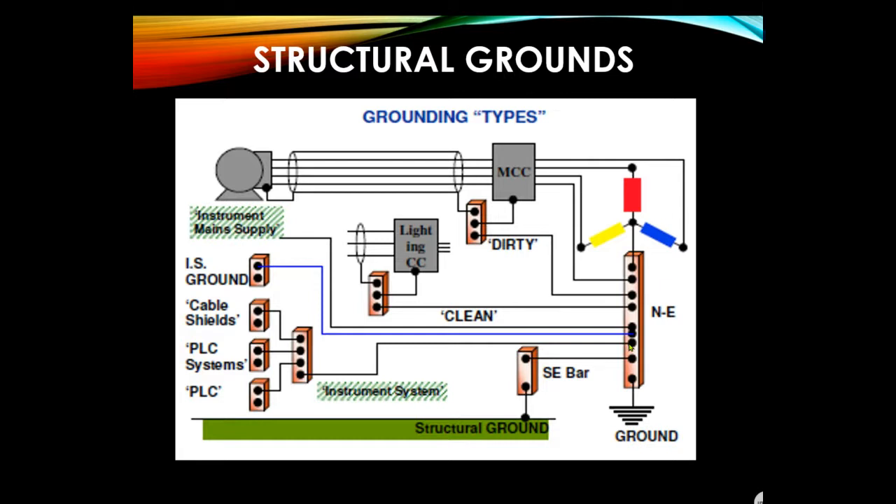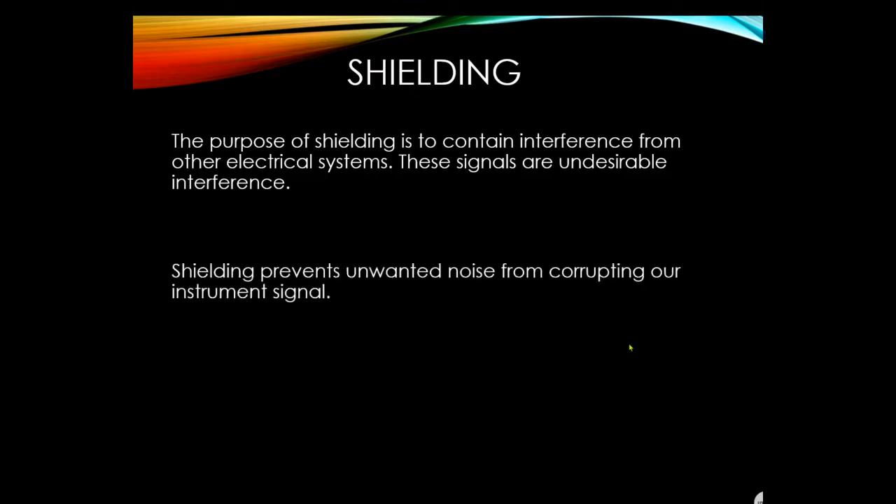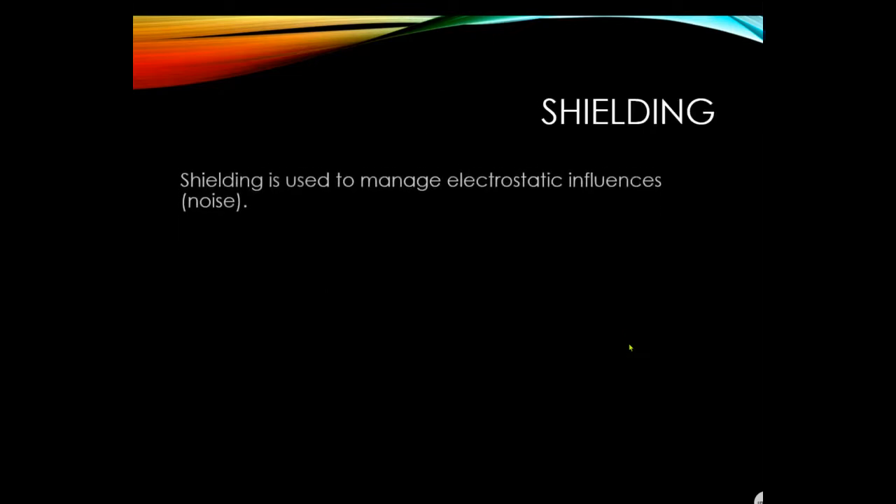The purpose of shielding is to contain interference from other electrical systems. These signals are undesirable interference. Shielding prevents unwanted noise from corrupting our instrument signal. Shielding manages electrostatic influences — called noise — and electromagnetic influences (EMI). Without shields, control cables can pick up this noise or electrostatic energy, resulting in a degraded signal.